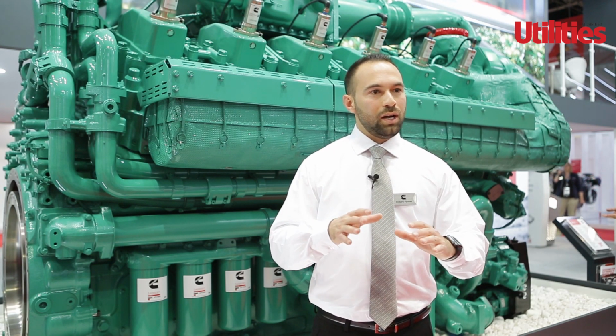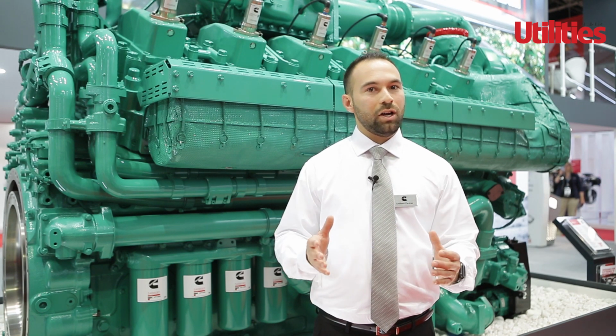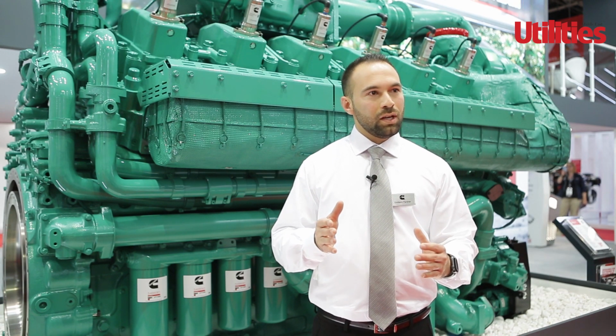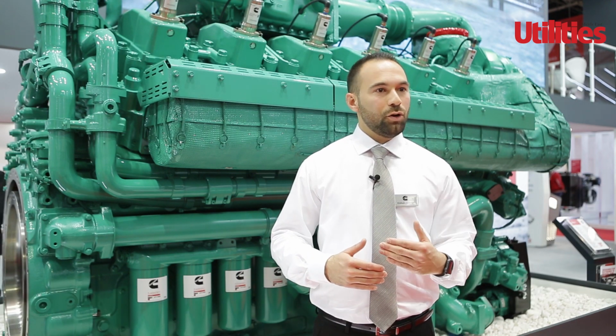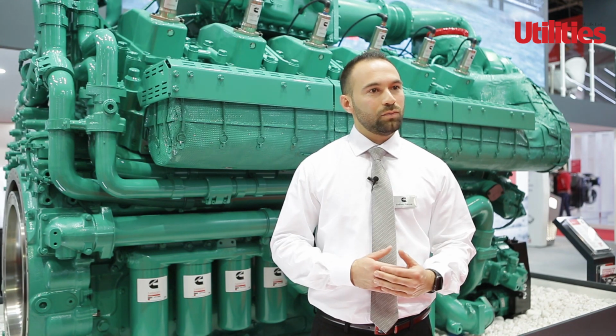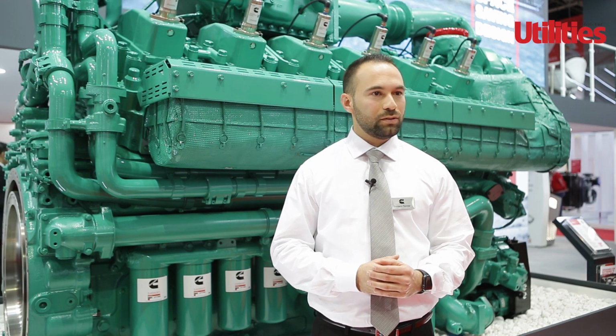Most of the power output is going to be at 2 megawatts, that's our highest rating of the machine, and we won't derate until we get to about a 70 methane number fuel, which is a great achievement. Obviously, as we go down in methane number on the fuel, we have to derate a little bit. At a 40 methane number, typically flare gas, the power output will be 1,600 kilowatts.